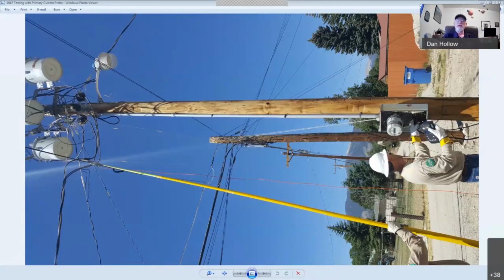And reading the information plate on these CTs, unless you have binoculars, and even if you have binoculars, these particular CTs were so washed out you could not read the plates even with binoculars. So that presents an additional challenge because you don't know what the accuracy class is, you don't know what the max burden is. You might be able to read the ratio because that's in big print, but that's one of the problems and challenges associated with testing CTs up on poles like this.